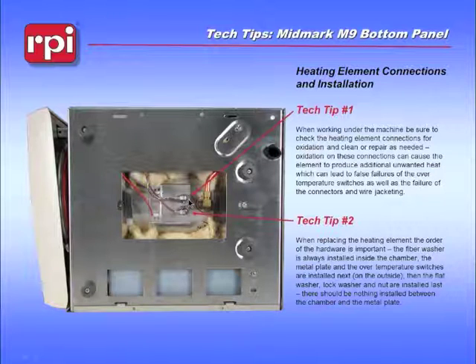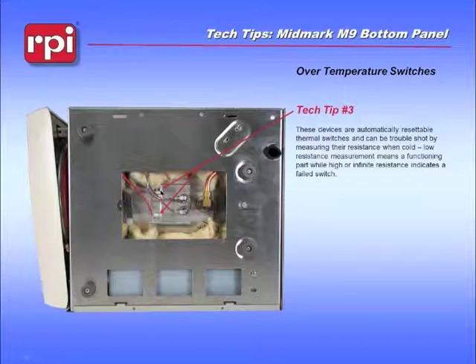The way this sealing system works is there is a single fiber washer that goes on the heating element bushing that goes inside the chamber. Then on the outside there is a second washer as well as a silver lock washer that's held in place by a nut. All those should be tight and sealed properly. We also have two temperature switches. These are over temperature switches that tell the machine when it has overheated. They are safety devices. They have to be functional.